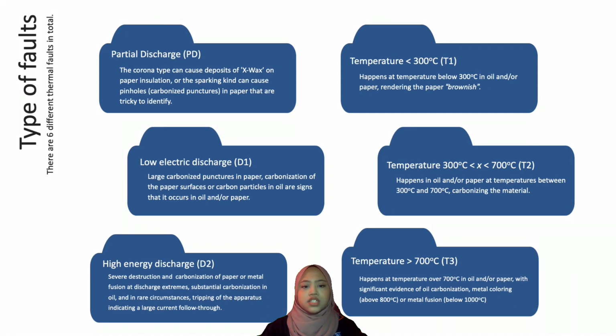First is partial discharge. The corona type can cause deposits of X-wax on paper insulation, or the sparking kind can cause pinholes in paper that are tricky to identify. Second is low energy discharge, D1. Large carbonized punctures in paper, carbonization of the paper surfaces, or carbon particles in oil are signs that it occurs in oil and or paper. Third is high energy discharge, D2. Severe destruction and carbonization of paper or metal fusion at discharge extremes, substantial carbonization in oil, and in rare circumstances, tripping of the apparatus indicating a large current follow through.